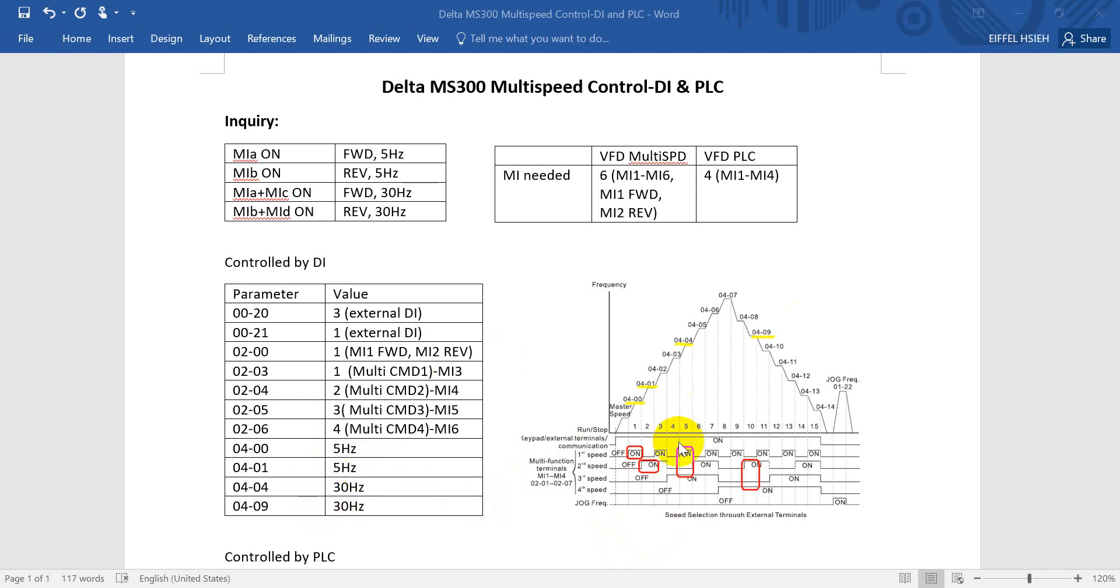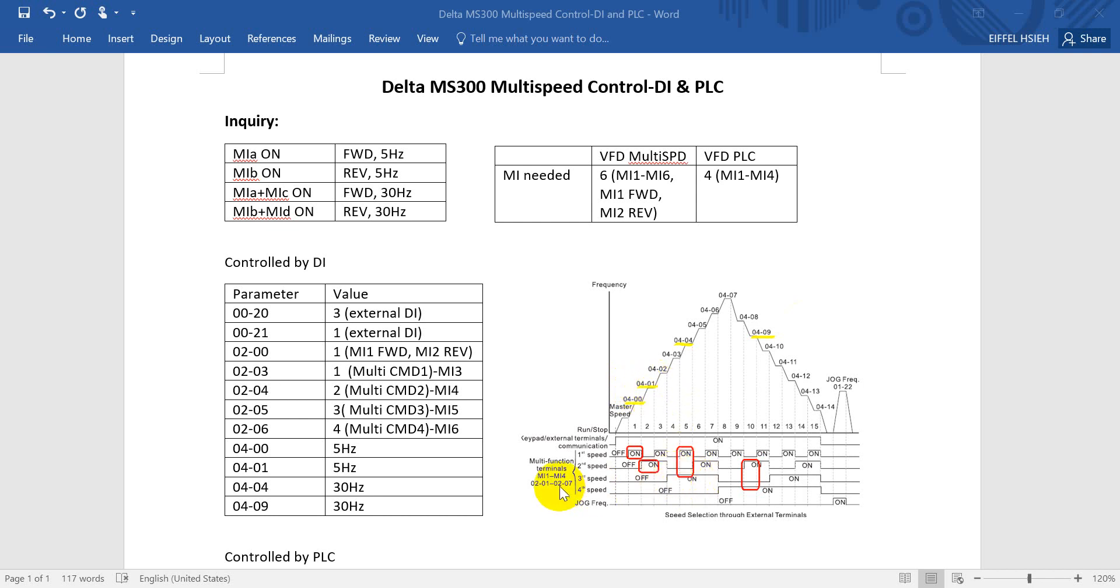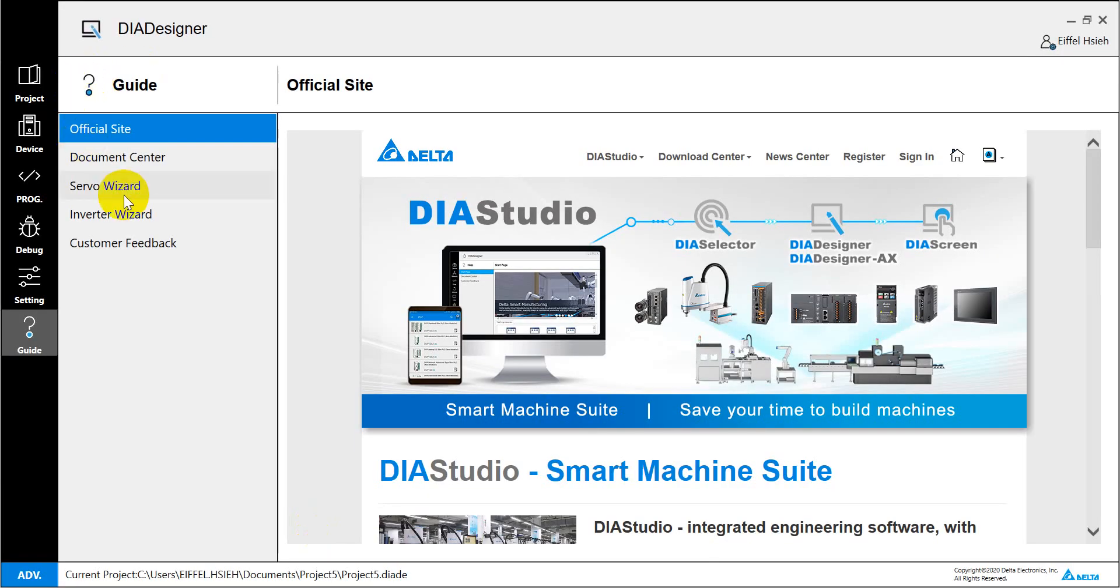Then we can define the different speeds over here. You can see when MI3, when MI1 on, that means we define the first step of frequency in 04.00. Then here is for MI2, which is relative with 04.01, and then would be the select MI3 and MI1. This one will map to 04.09.